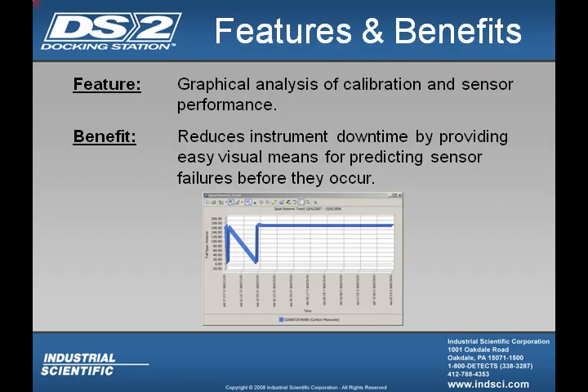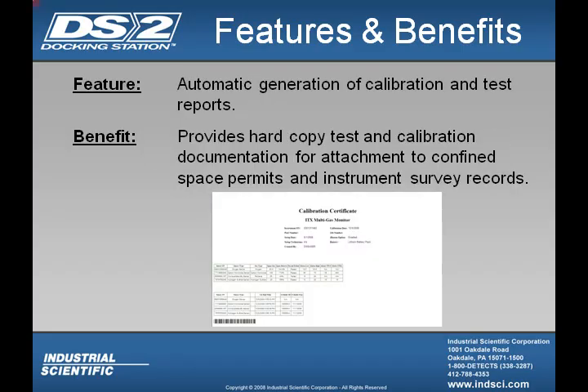You also have graphical analysis of all your calibration and sensor performances. And this will reduce instrument downtime, providing an easy visual means for predicting sensor failure before it actually occurs. And now all your calibration records can be automatically generated. And what this provides is hard copy test and calibration documentation for attachment to confined space permits and instrument survey records.